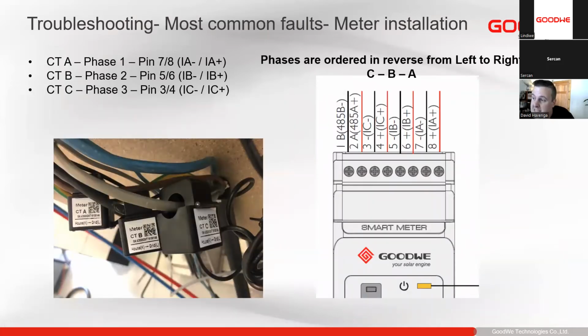When we install our CTs, sometimes we might think they're backwards. So if you look at the CT wiring here on top, you'll see CTA is on 7 and 8, CTB on 5 and 6, and C on 3 and 4. So they're from right to left on top of the smart meter. Please always pay attention to this.